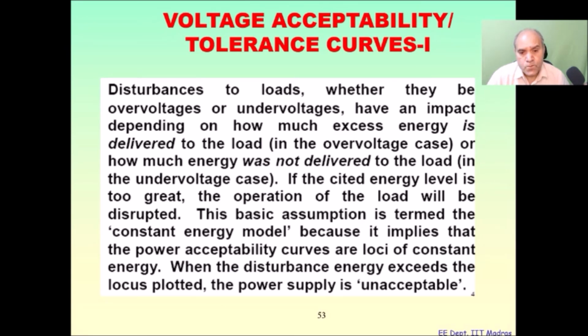Okay, we know that any device has some maximum or minimum voltage limits for which it can operate faithfully. If the voltage is very high, it is likely to be damaged. If the voltage is very low, it may not even switch on. So this kind of behavior is basically called the voltage acceptability tolerance curve.